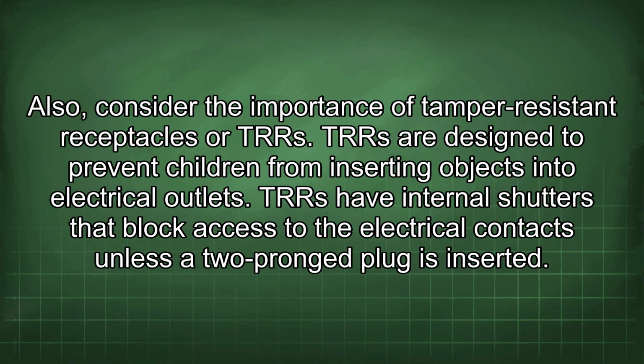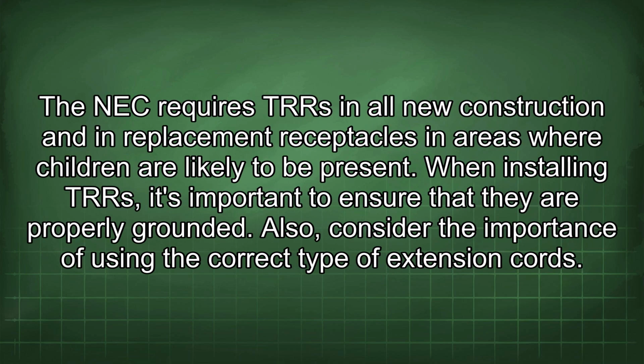Also, consider the importance of tamper-resistant receptacles, or TRRs. TRRs are designed to prevent children from inserting objects into electrical outlets. TRRs have internal shutters that block access to the electrical contacts unless a two-prong plug is inserted. The NEC requires TRRs in all new construction and in replacement receptacles in areas where children are likely to be present. When installing TRRs, it's important to ensure that they are properly grounded.